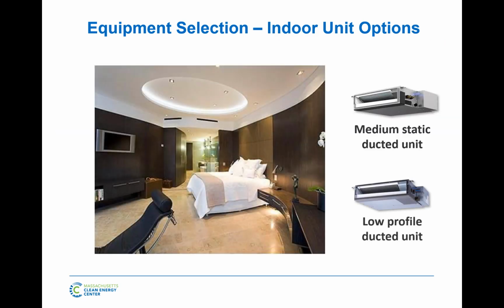Then we get into the ducted unit. Ducted units are probably half of what's being sold in the United States, to the point where most of the time when I deal with our headquarters in Japan, one of the biggest questions they have is, why do you guys keep buying more and more ducted units around here? It's just conventionally what we're used to in the US. There are several different types of ducted units. They're typically broken up by both size, so capacity, how many BTUs they can deliver, and then static pressure, which is how much ductwork they can handle.